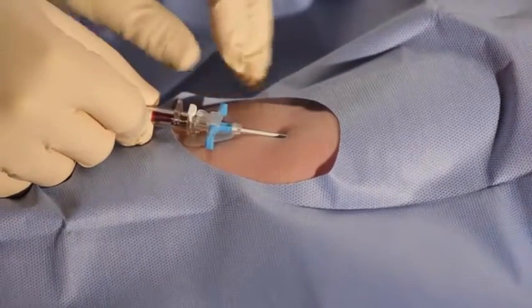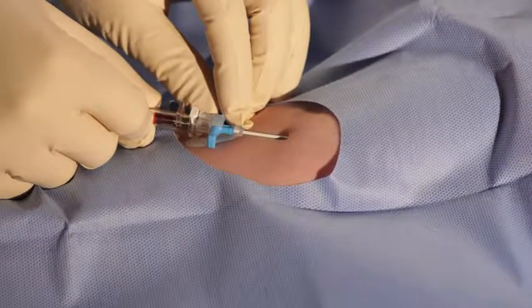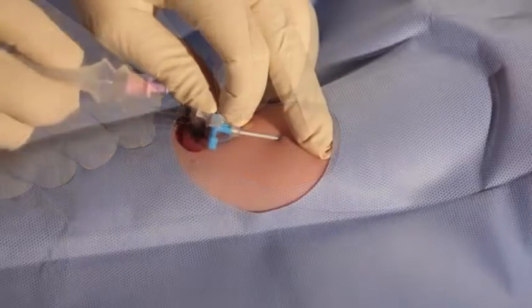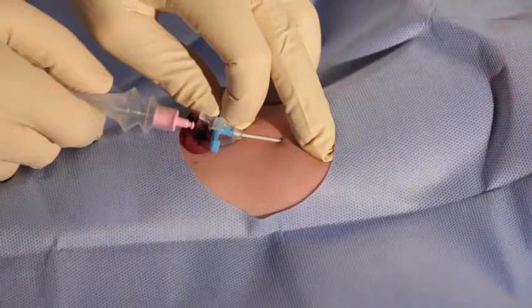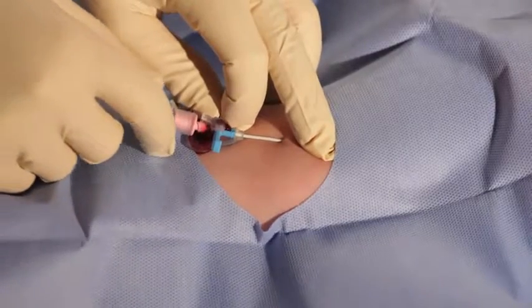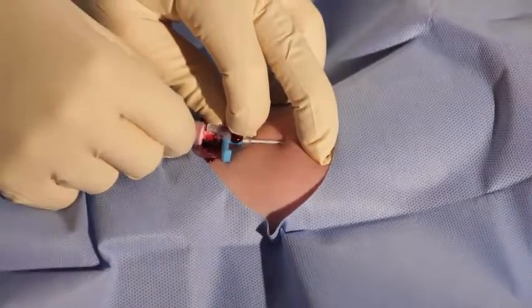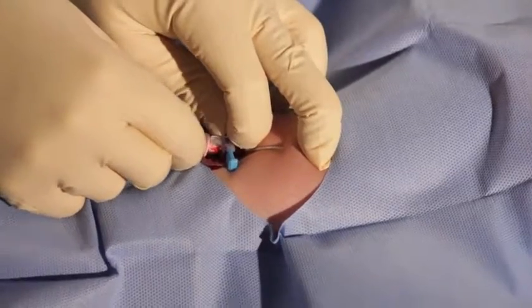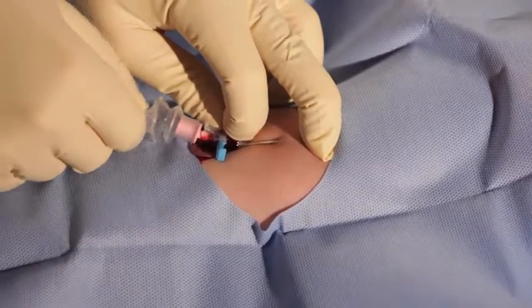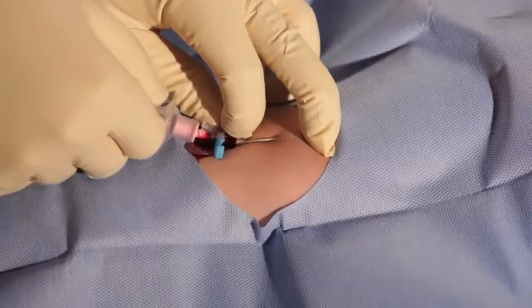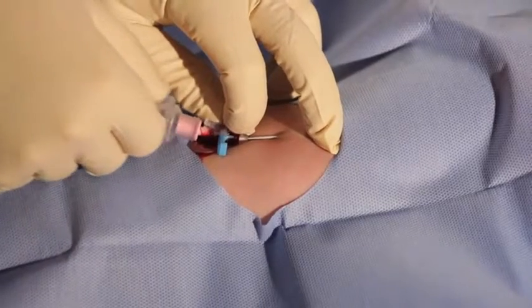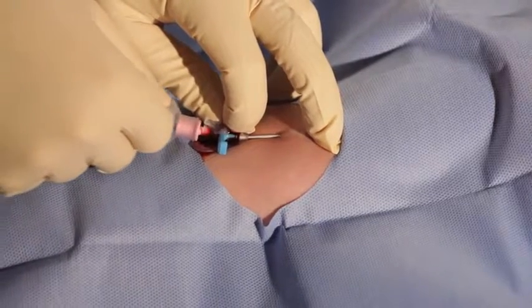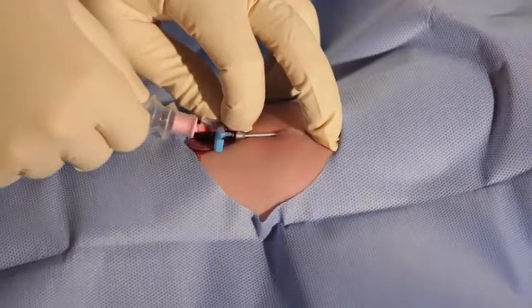When fully inserted, remove the needle and apply digital pressure to the vein above the introducer tip to slow the backflow of blood. Push the button to activate the needle safety feature. Firmly insert the tip of the M29 into the hub of the peel guard until it clicks into place. Grasp the sterile drape and loosen the tourniquet to allow the catheter to be advanced. Advance the M29 by grasping the catheter behind the bellows.